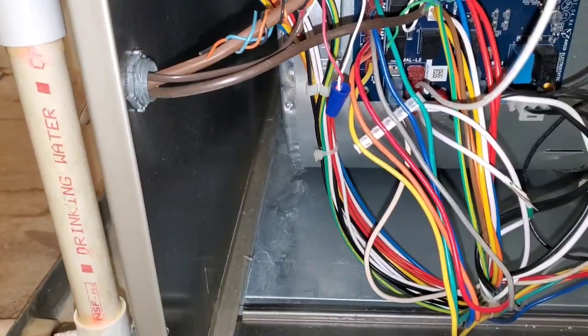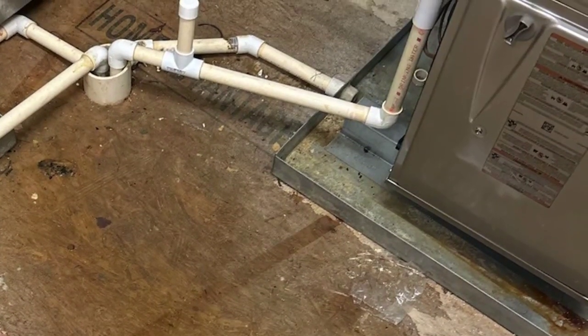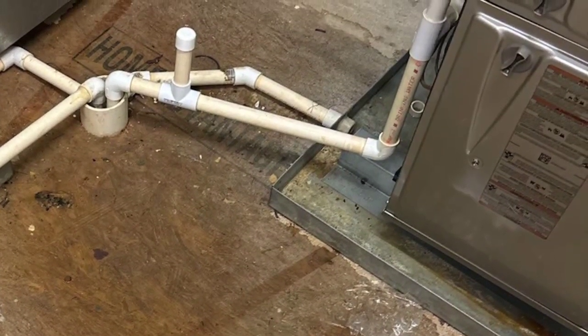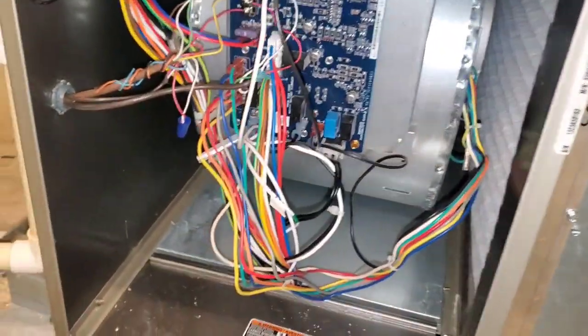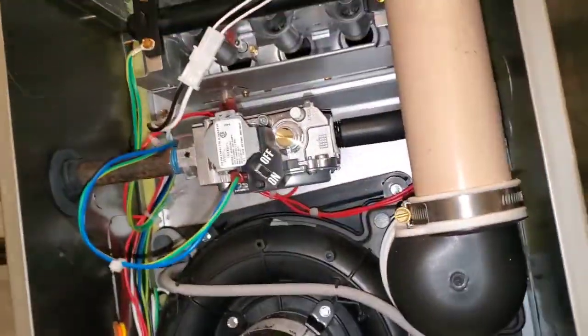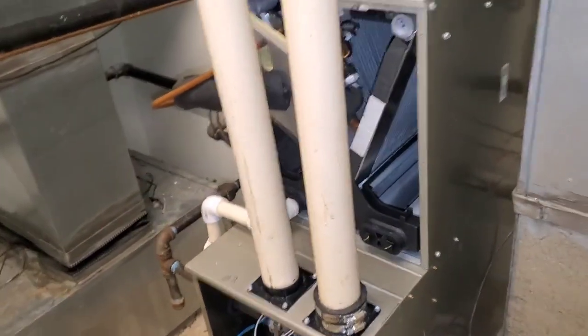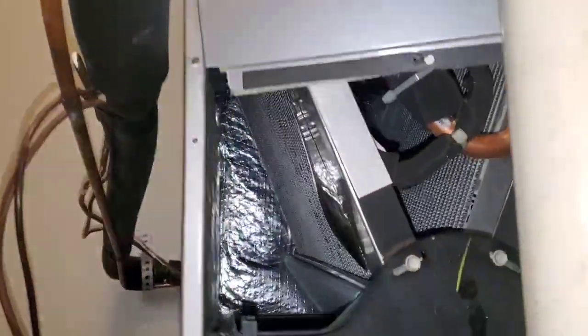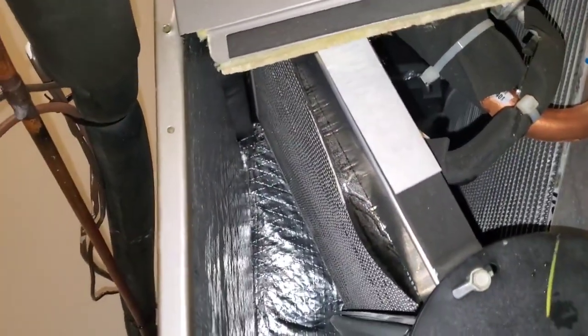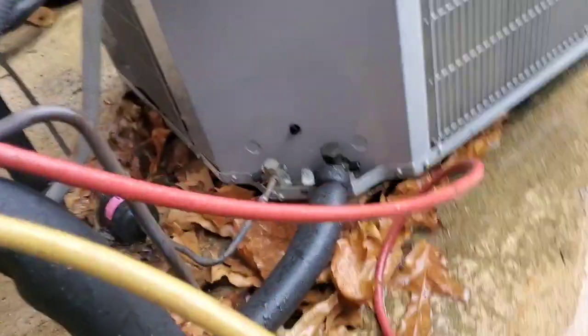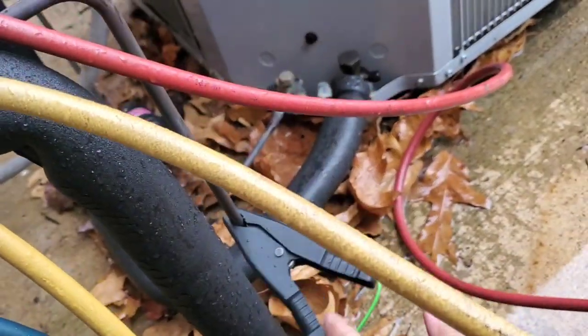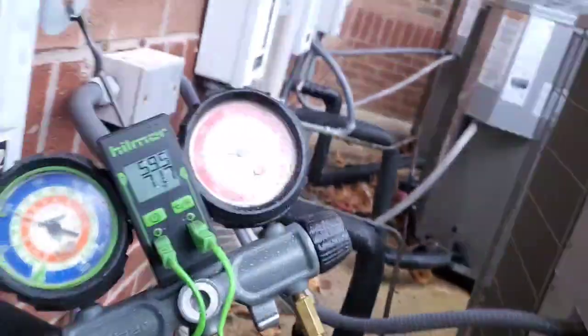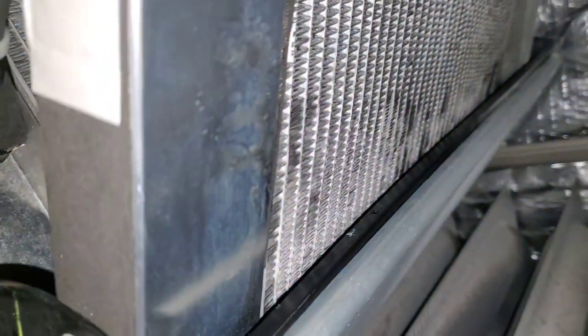But I have this picture that shows what it looked like when the call came in. Mr. Maintenance guy that took all the screws out. That'll happen if the water was dripping off the side of the evaporator, just raining down, which sometimes happens in these V coils. I'm gonna move the liquid line probe to the other side of the filter dryer. In the evaporator section, we have a frost pattern.